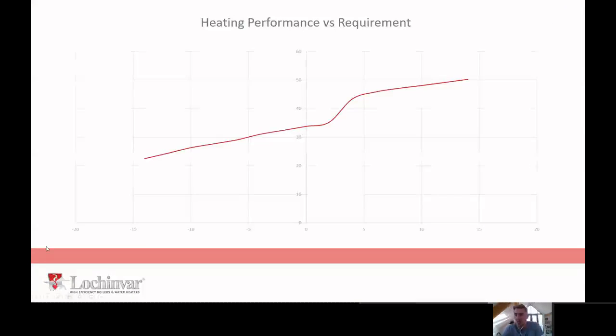Okay, so what we have on the screen at the moment is a graph, and along the bottom of that graph is the outside air temperature. This is the condition that the air source heat pump is going to be operating in. The air source heat pump is going to be external plant. The range it will work in is greater than this, but typically they'll work down to -20. The graph just happens to be plotted up to +20, so that's our outside air temperature.